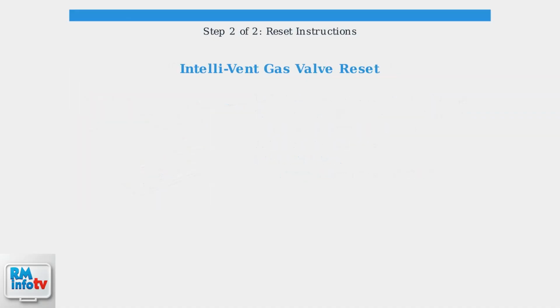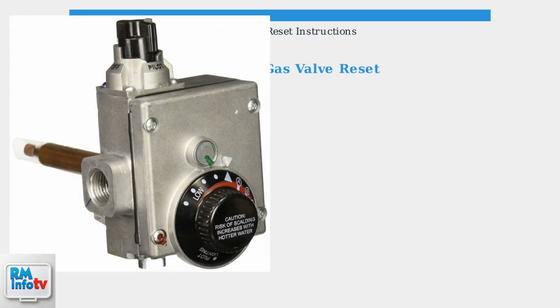The second common type is the IntelliVent gas valve. This reset procedure is timing sensitive, so follow each step carefully within the specified time limits. This is a typical gas control valve. The IntelliVent system uses temperature adjustment buttons and LED indicators for the reset process. Start by turning off power for exactly 10 seconds, then restore it. The next steps are time critical and must be completed within specific windows.